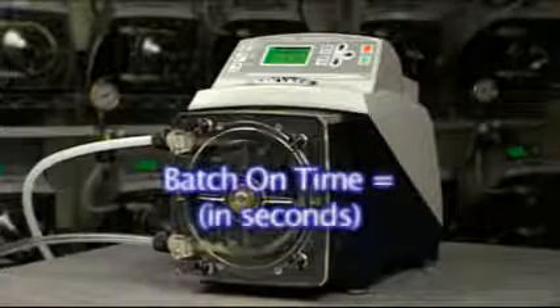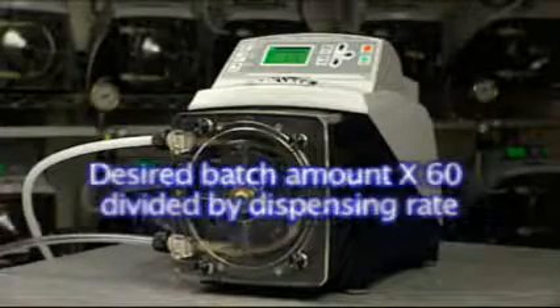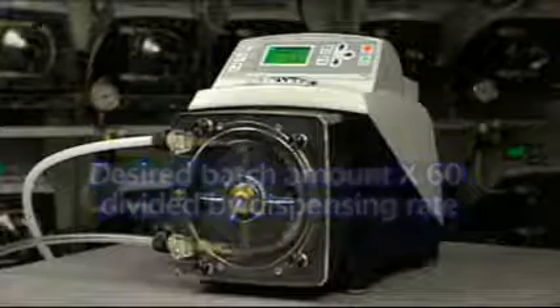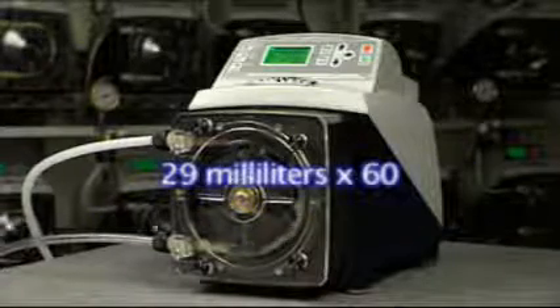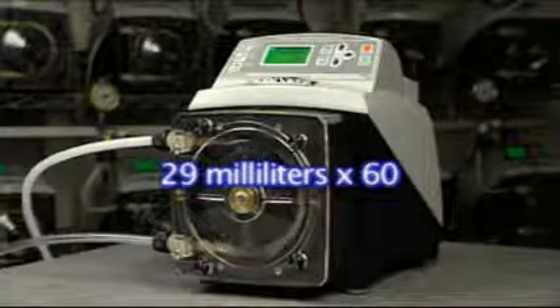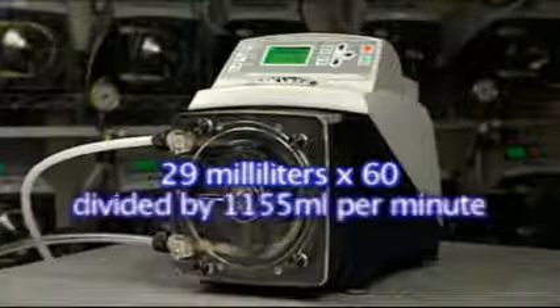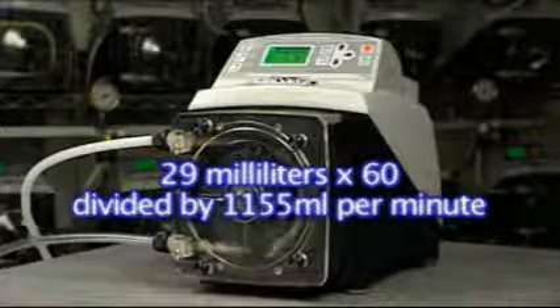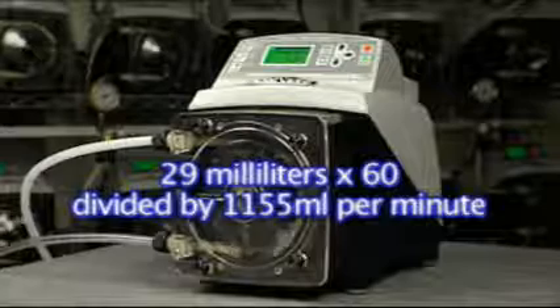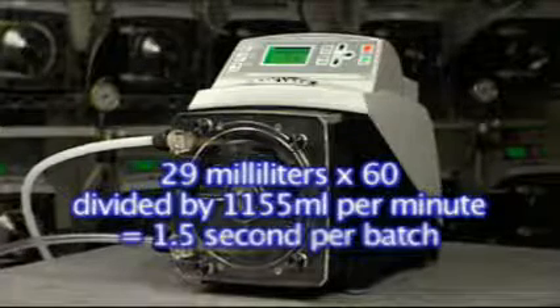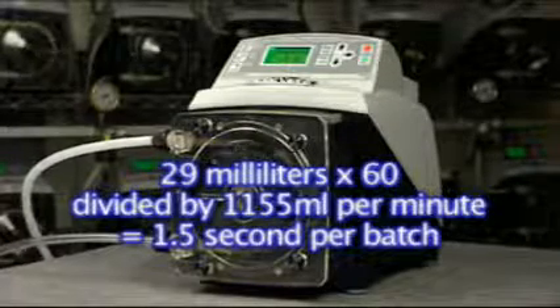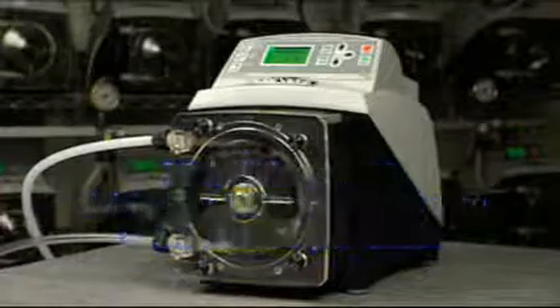Next, determine the seconds of pump run time required to inject the desired amount of chemical. For example, if the desired amount of chemical per batch is 29 milliliters and the pump is set to output at a rate of 1,155 milliliters per minute, then the pump on time per batch should be set for 1.5 seconds.